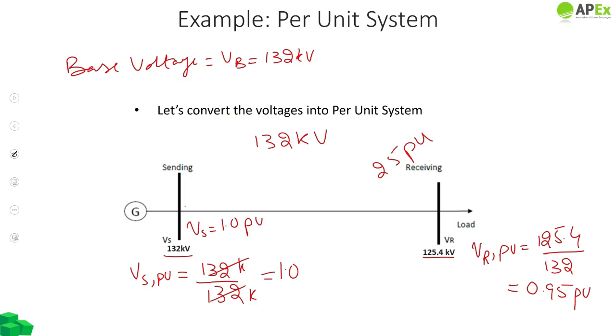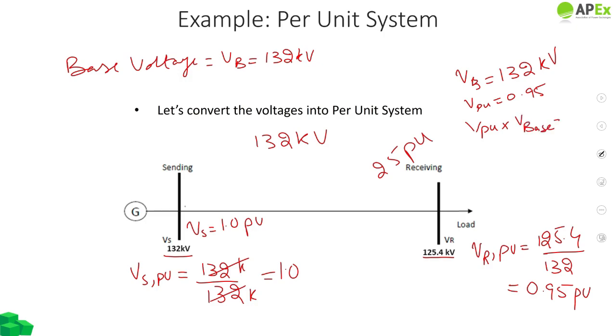Now let's do vice versa of this example. Let's say we were given a base value of voltage to be 132 kV, while our per unit value at that instance was 0.95. How would we obtain the value in kilovolts? What we would do is multiply our per unit value of voltage with the base value. And this would give us what we call V actual, or the value in kV.